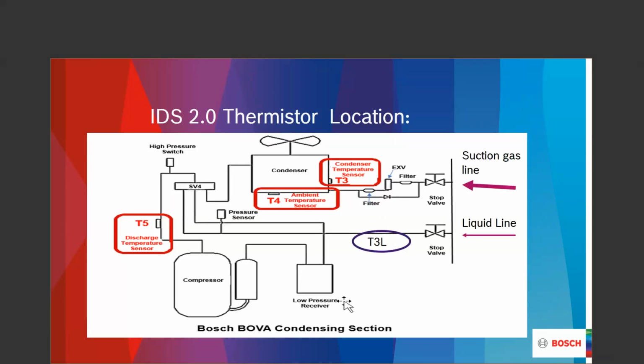It allows the serviceman to now get the subcooling reading, what we would call the true reading of the liquid line temperature, so he can now get subcooling without putting a liquid line sensor clamp on the liquid line like he would have to do with the 1.0. So in the 2.0, man, there's a lot of things that you can literally leave in the truck and sit on a bucket and look and push a button and record those parameters and get your diagnostics from that.